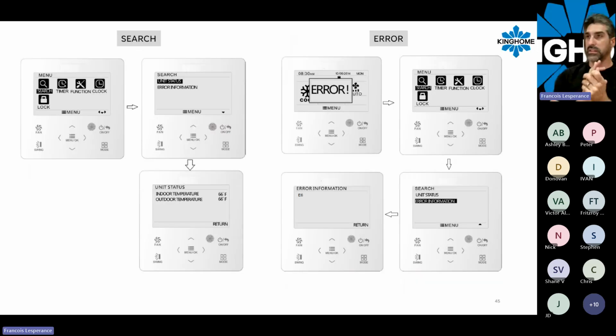The thing that is pretty neat with this controller is that it can help you do a little bit more troubleshooting when you have some issue with the system. So basically, if you click on the menu button, you can click on the search button, unit status, and then the system will tell you the indoor temperature sensor reading and also the outdoor temperature sensor reading. So you can know exactly what is going on, what temperature the unit is reading right now. If an error occurs while you are using the system, an error window will pop up, and by clicking on search error information, you can see what error code it is related to.